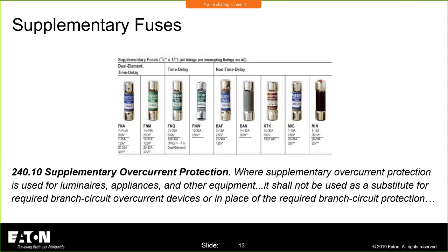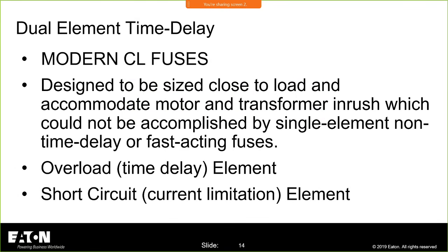Okay, so that's your supplementary, and we have supplementary circuit breakers and supplementary fuses. They all work alike. Dual element time delays. You'll actually see this in the National Electrical Code. What's the article on motors, 430? Yep, 430 on motors, 430.52 talks about dual element time delay fuses and then non-time delay fuses when you're talking about motors.